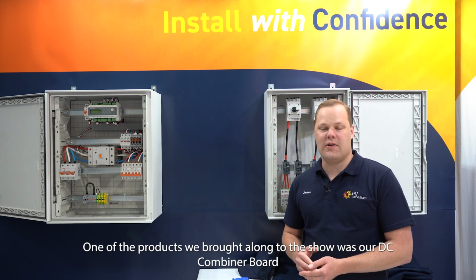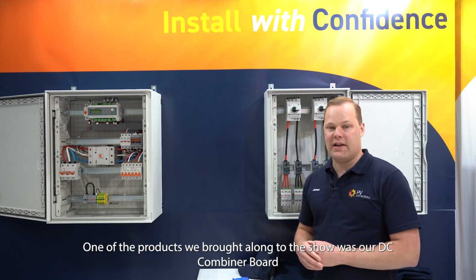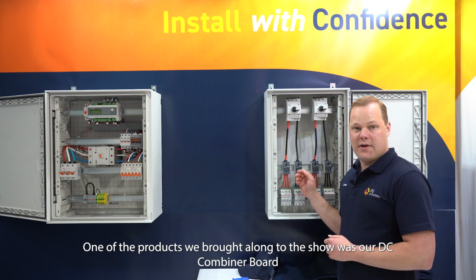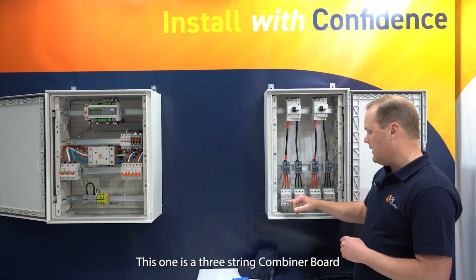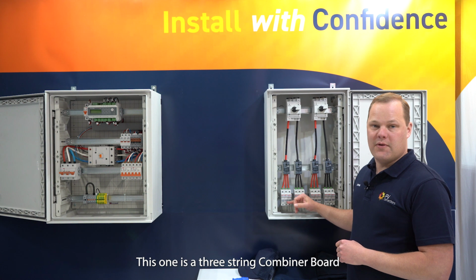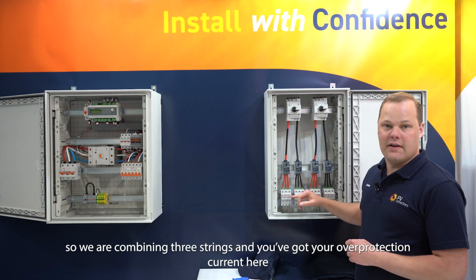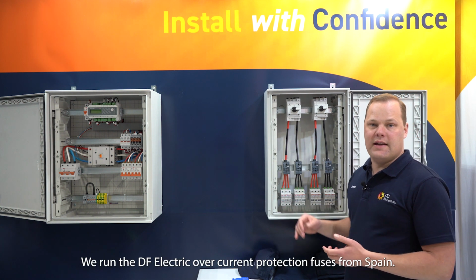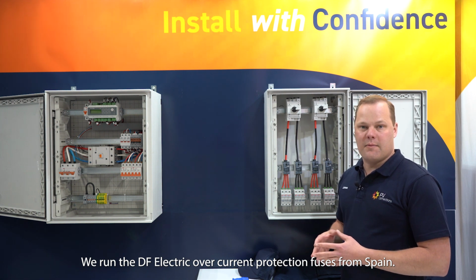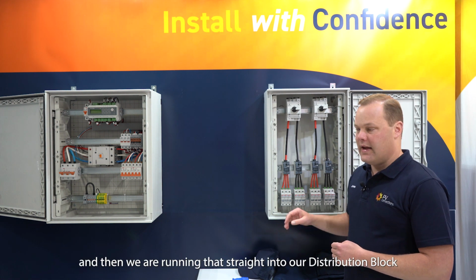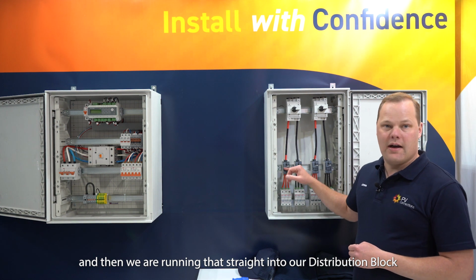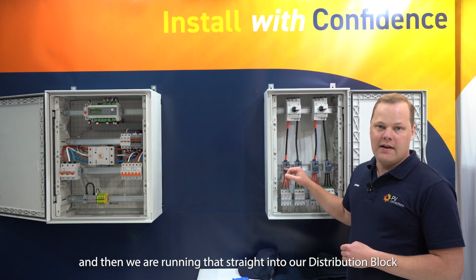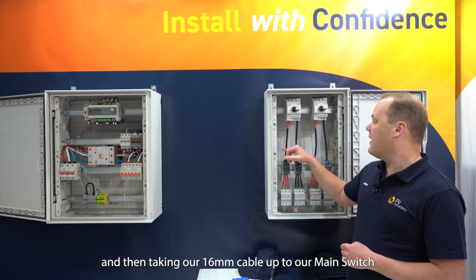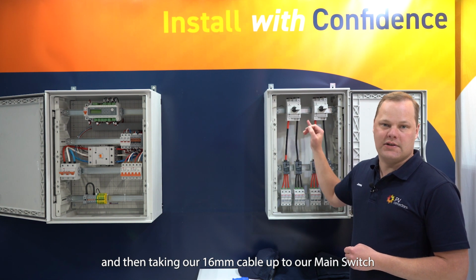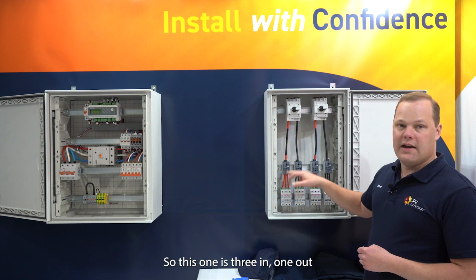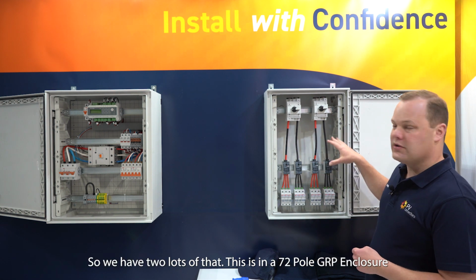One of the products we brought along to All Energy 2023 is this DC combiner board. This one is a three-string combiner board, so we're combining three strings. You've got your overcurrent protection here, running DF Electric overcurrent protection fuses from Spain. Then we run that straight into our distribution block, paralleling it in there, and take out our 16 mil cable up to our main switch. This one is three in, one out, and we've got two lots of that in this unit.